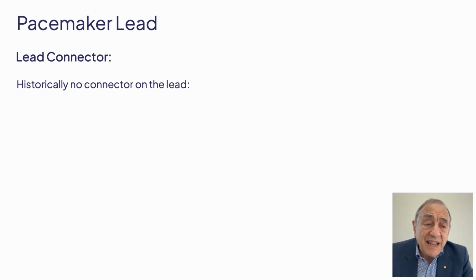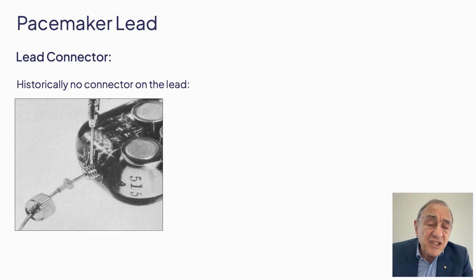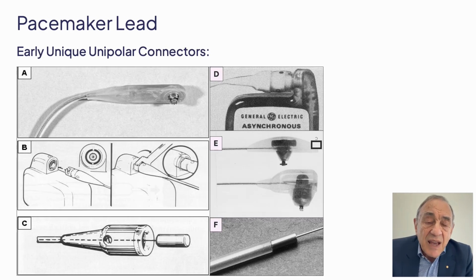Historically, we know there was no connector on the lead, and this was created at the time of implantation of the pulse generator, and it wasn't a particularly satisfactory lead. As a result, we had a number of unique unipolar connectors, with each company creating their own design. This caused chaos because, at the time of pacemaker replacement, the pulse generators had gone on to a new design, and the connectors had to be cut off and another connector placed on the lead.